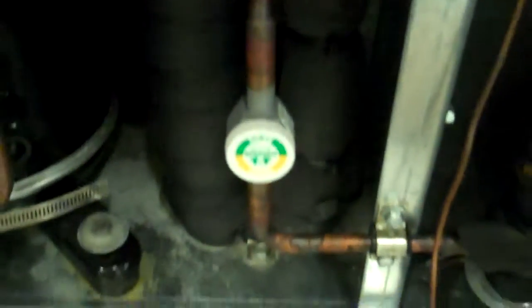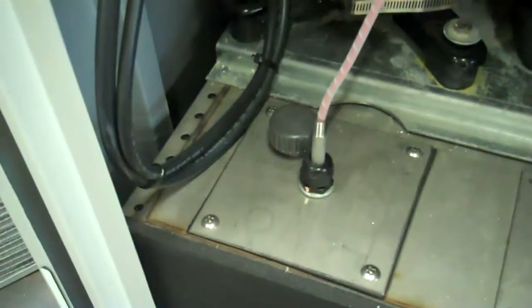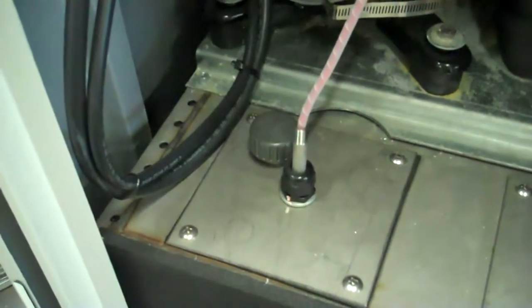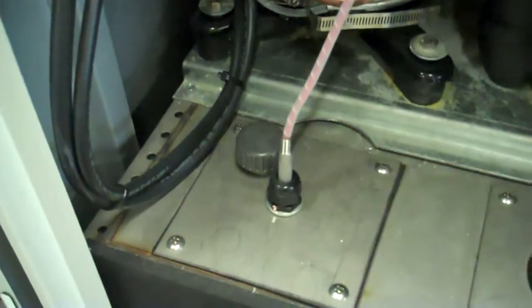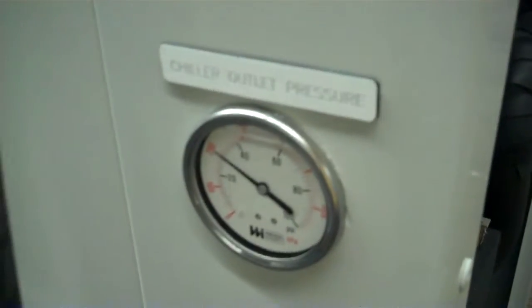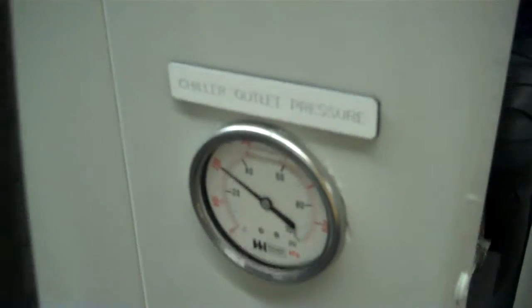our fill for the tank, our sight glass for the refrigerant. There's a thermal expansion valve there. We actually have a built-in level sensor for the tank, which will automatically shut off if the tank volume gets too low. We also have our sight glass here, so you can see the level of the fluid in the tank. We've also got a nice little drain on the bottom there. We do have a gauge for the pump pressure. It's operating at a nice 30 psi.